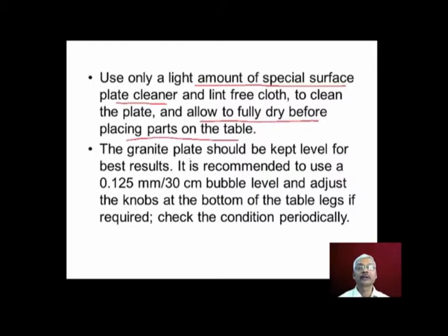The granite plate should be kept level for best results. We should use a 0.125 millimeter per 30 centimeter bubble level, and we should adjust the knobs at the bottom of the table legs. If required, we should check this condition periodically.